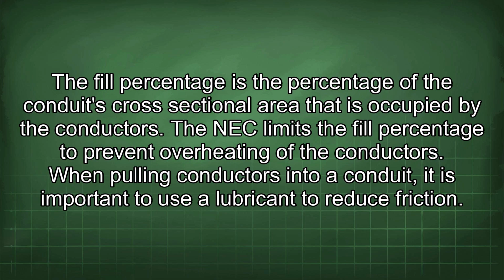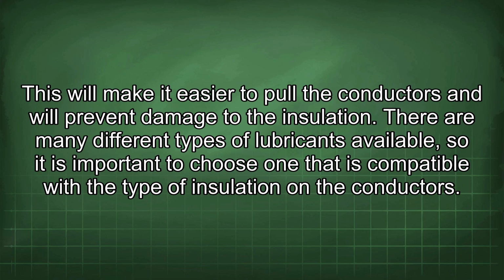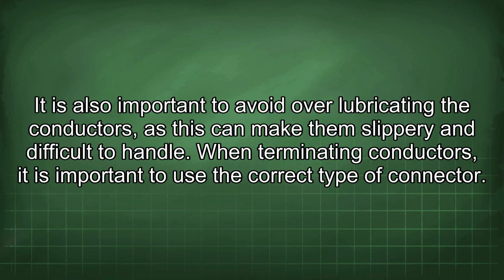When pulling conductors into a conduit, it is important to use a lubricant to reduce friction. This will make it easier to pull the conductors and will prevent damage to the insulation. There are many different types of lubricants available, so it is important to choose one that is compatible with the type of insulation on the conductors. It is also important to avoid over-lubricating the conductors, as this can make them slippery and difficult to handle.